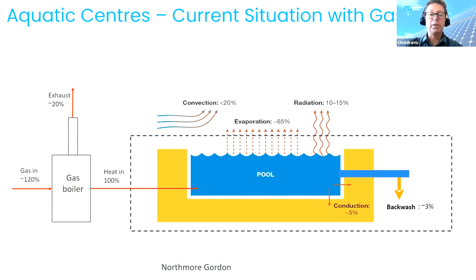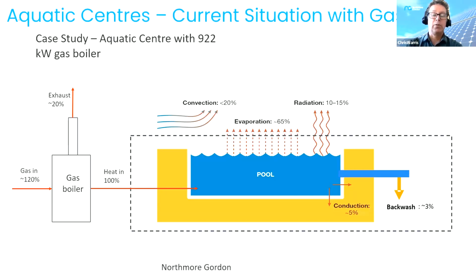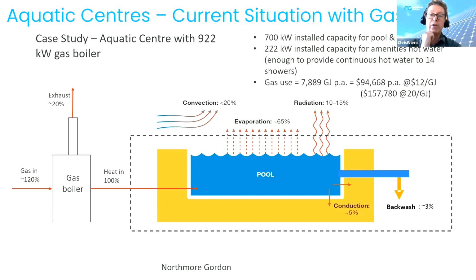So the simplest way is just to replace that gas boiler with a heat pump that's the same size. If we look at an example of an aquatic centre with a 922 kilowatt gas boiler, which is a medium-sized aquatic centre, it's got 700 kilowatts of installed capacity for the pool and air heating, and 222 kilowatts of installed capacity for the amenities hot water, and that's enough to provide continuous hot water for 14 showers.